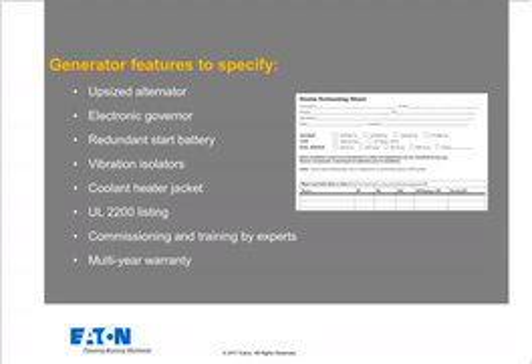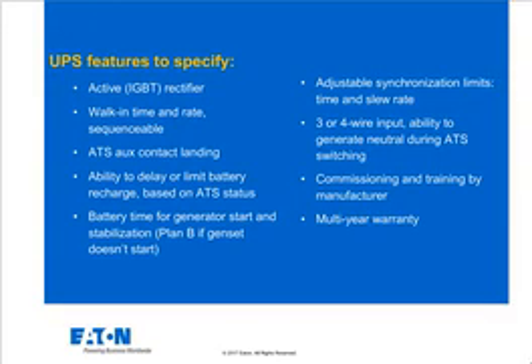Other things like a coolant heating jacket in cold environments to make sure that the generator starts as quickly as possible when it's needed, and of course commissioning and training by actual experts. The generator distributor will likely have well-trained people that can come out and do the commissioning and make sure everything is set up just right.